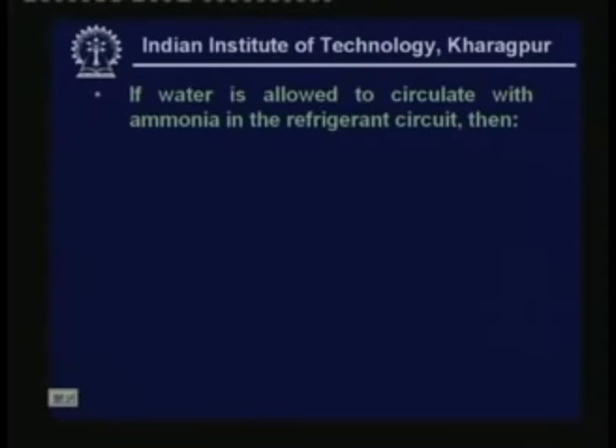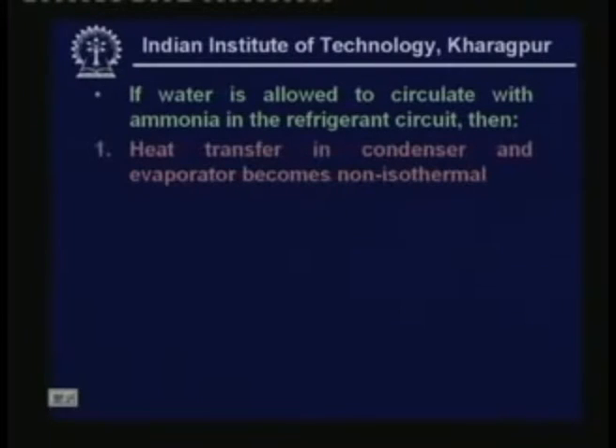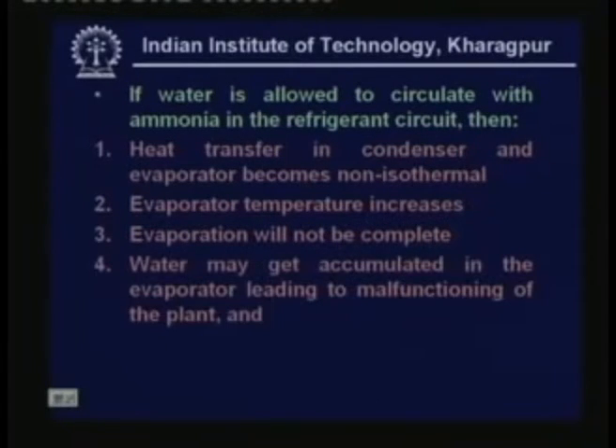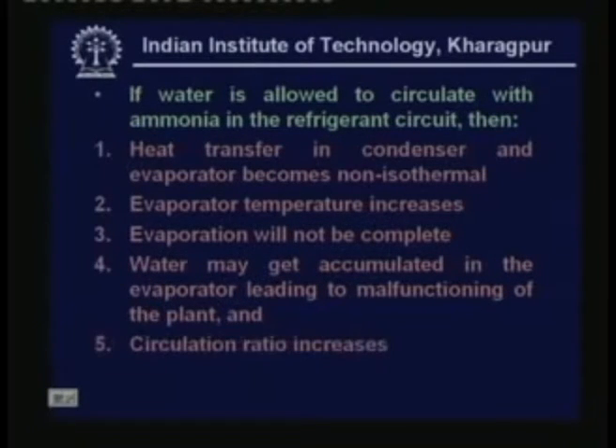If water is allowed to circulate with ammonia in the refrigerant circuit, the problems are: first, heat transfer in the condenser and evaporator becomes non-isothermal; then evaporator temperature increases; evaporation will not be complete; water may get accumulated in the evaporator leading to malfunctioning of the plant; and finally the circulation ratio also increases. All these effects are detrimental to system performance.